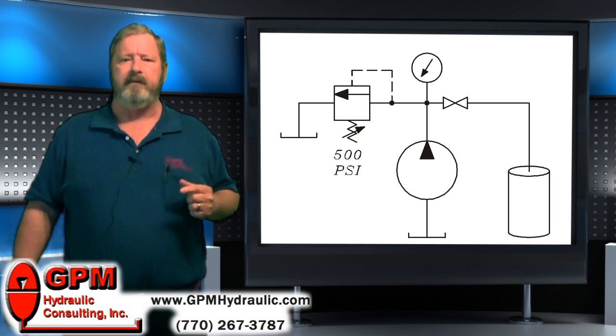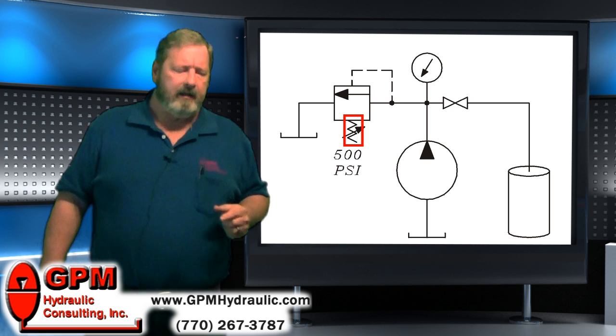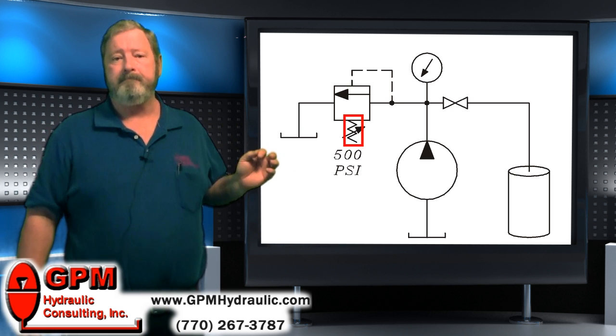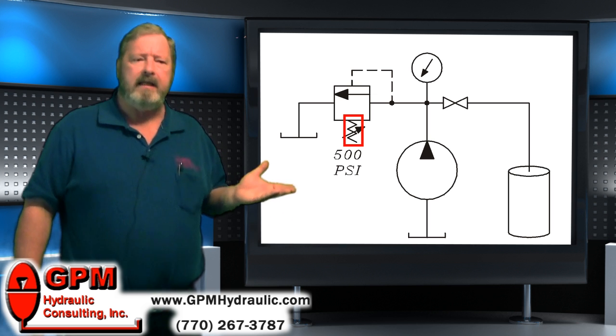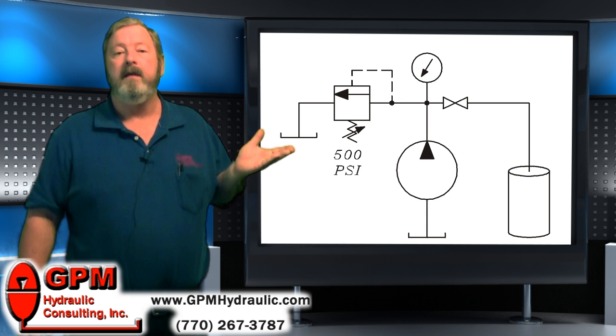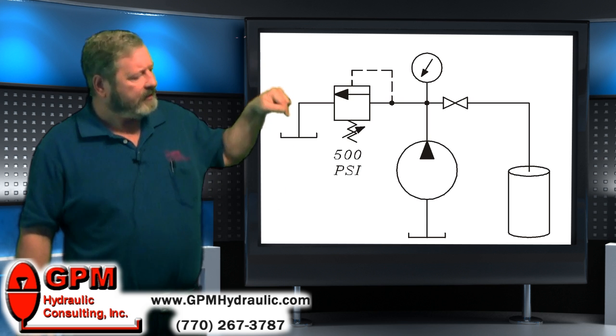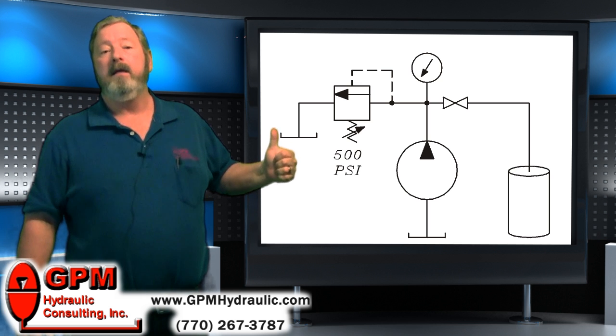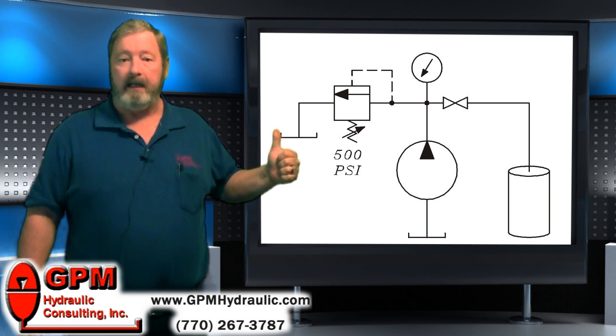A good way to think of a relief valve on a schematic, you see this jagged line under here, that indicates a spring, and think of the spring as pushing the arrow up away from the ports, holding the valve closed. This means that something needs to push down harder than the spring is pushing up in order for the valve to open and allow flow.